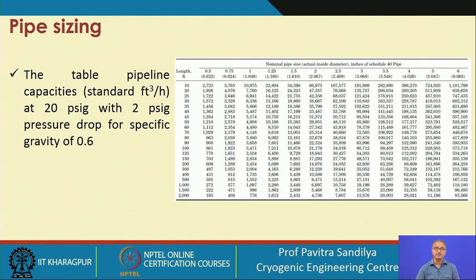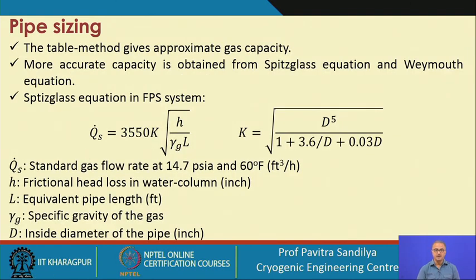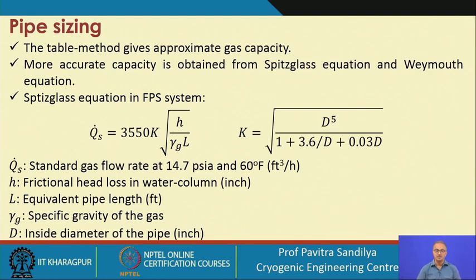The capacity depends on specific gravity — this table is given for a specific gravity value of 0.6. The table gives approximate gas capacity; more accurate capacity is obtained using the Spitzglass or Weymouth equations. The Spitzglass expression for the FPS system can be used to find the actual capacity in the pipeline.